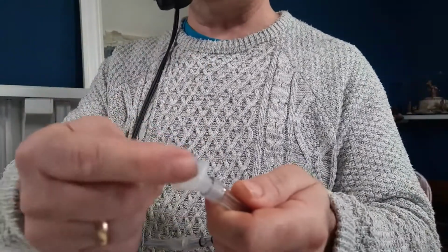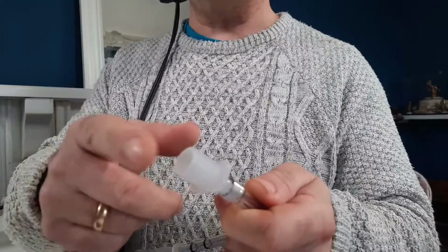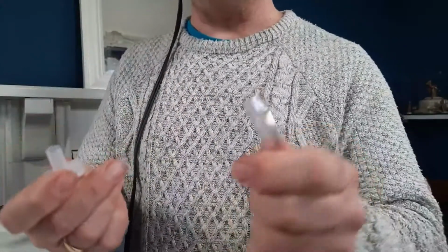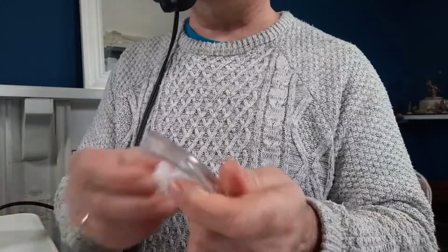So if I take this connection off, the plastic connection at the end is a 15mm connector. Again, that's the internal diameter, which will connect to your ventilator, and you can take that out. You just twist it and it pulls out.